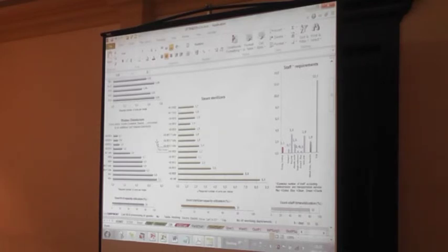If we don't like, we can just use the first page, 17,000 operations, that's it, or go very, very deep into each kind of surgery: general surgery, orthopedic, how many inpatient, outpatient surgery, and go very deep, or very shallow. And we do see how many spray baskets are needed, or containers, exactly in the numbers, also how many washing parts are needed, and detergents. So it's quite a lot in there to help the designer to design the perfect system.